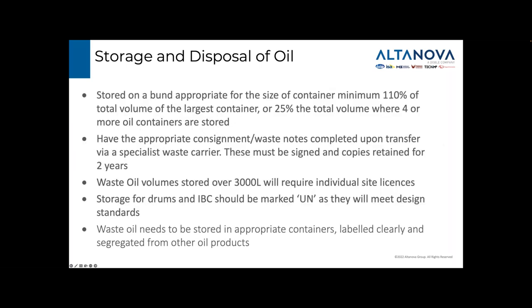The bund size you require actually depends on the size of storage container. Typically, a minimum of 110% of the largest container's volume. You must prepare consignment paperwork in advance for collection and use a specialist waste carrier for removal from site. The paperwork must be signed and retained for 2 years. If you're storing 3 kilolitres of oil or more at your place or location, you will need a site licence to avoid penalty. Storage containers like IBCs should have the UN markings. This indicates they meet the required design standards. Waste oil is best stored like new oil or unused oil. However, it should be segregated to avoid cross-contamination with other oils and other oil types.